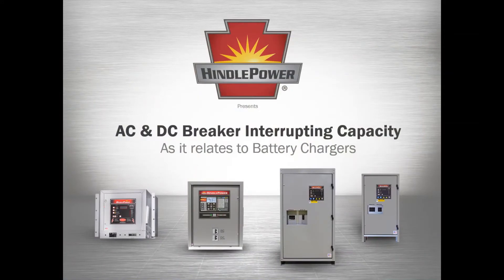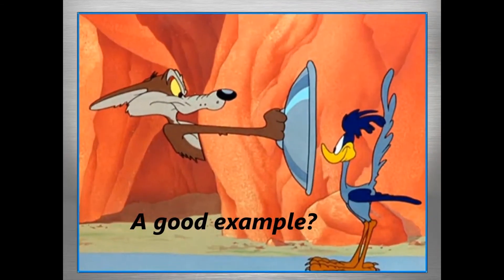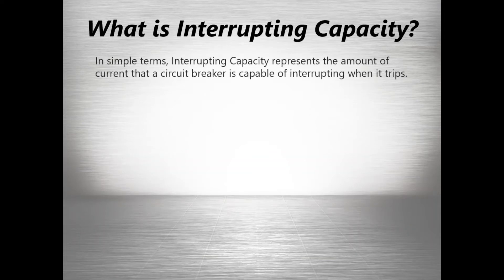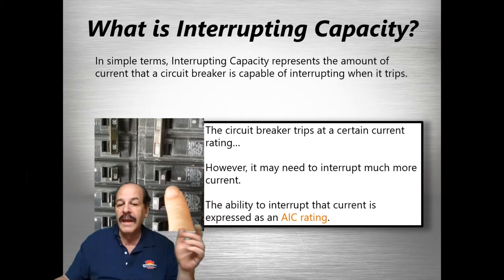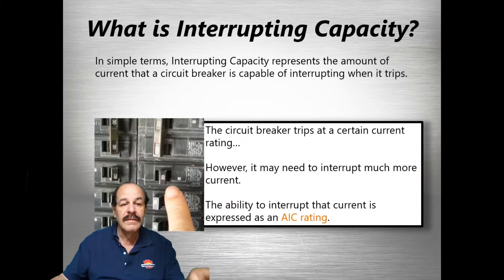Let's start discussing AC and DC interrupting capacities as they relate to battery chargers, beginning with what interrupting capacity actually is. In simple terms, we're talking about exactly how much current a circuit breaker can actually interrupt. The key term here is AIC — Ampere Interrupting Capacity — and the AIC rating deals with how much current the breaker can actually stop, which will exceed its trip rating by some number.